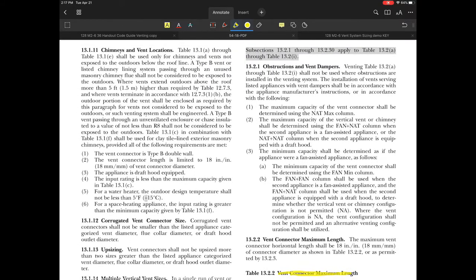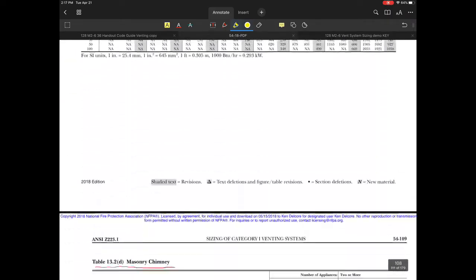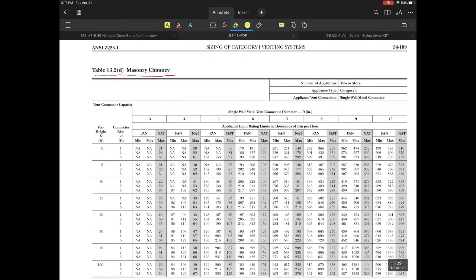Those are part of the rules identified in chimneys and vent locations — vent connectors are limited to 18 inches per inch of the vent connector diameter. It's always a good idea to review those prior to putting your stamp of approval on something. So let's go back to table 13-2-D. That sizing system is going to identify two or more appliances. We have a category one appliance and we are dealing with single wall metal vent connectors, so that is the correct table.